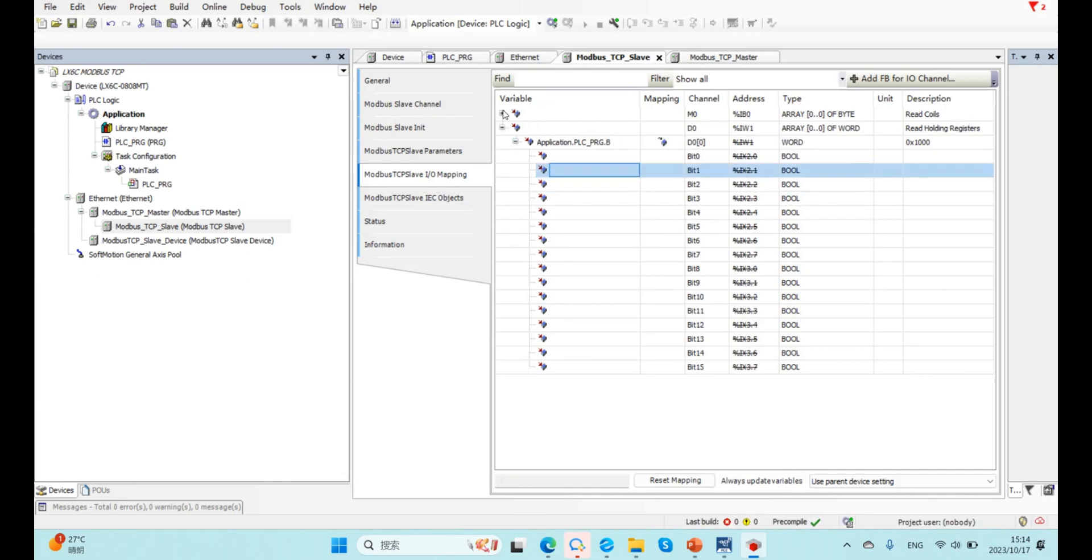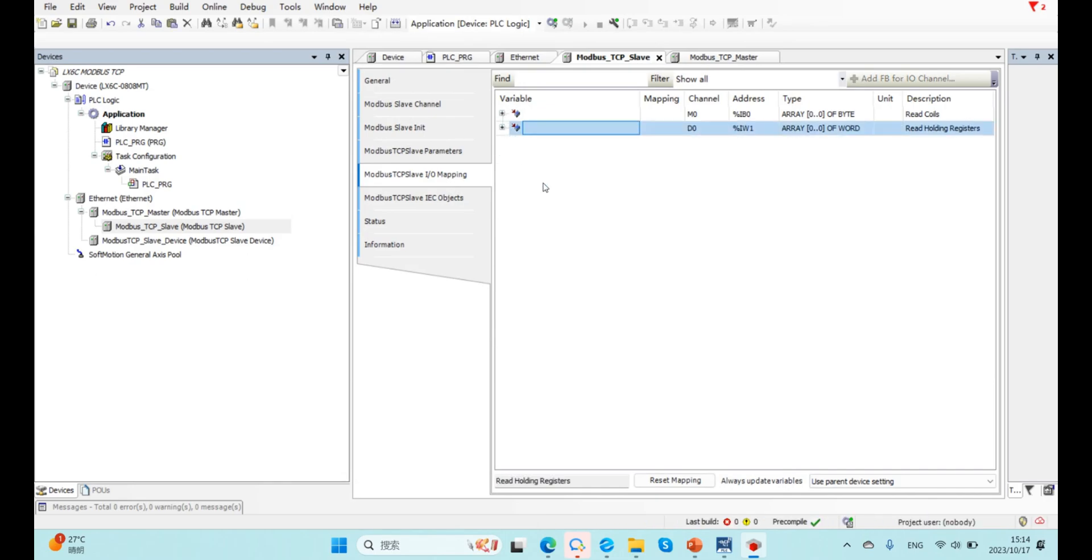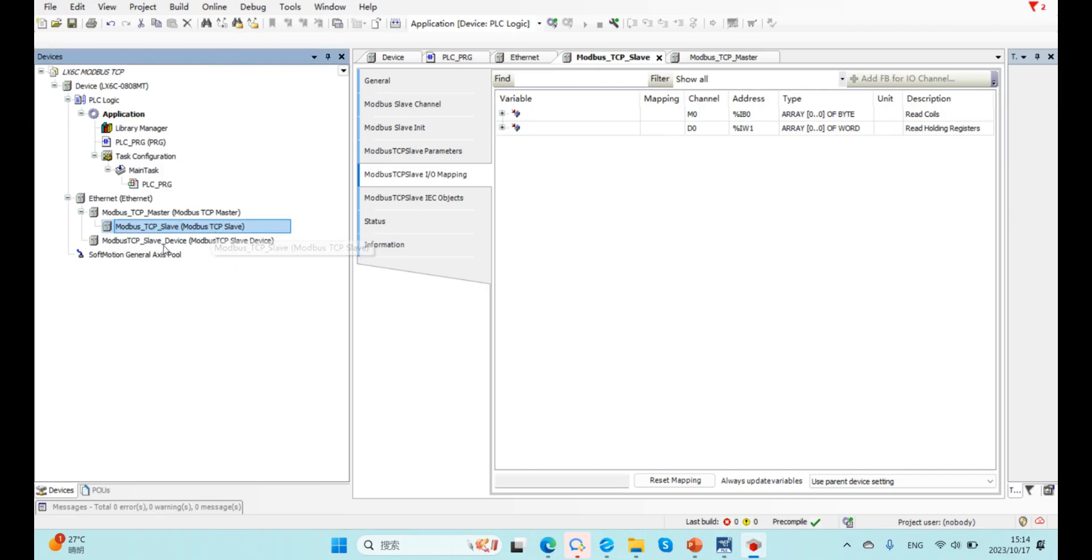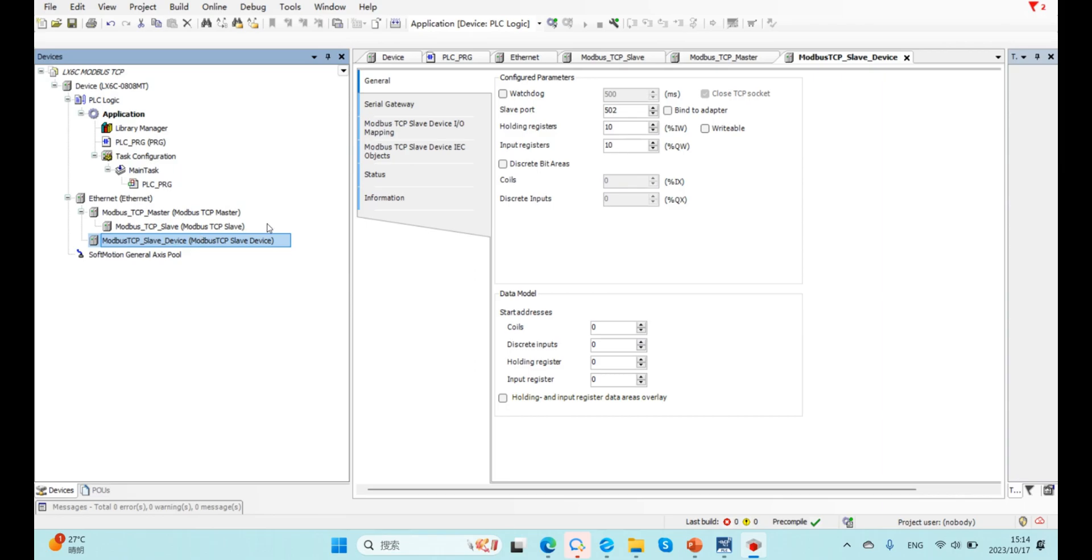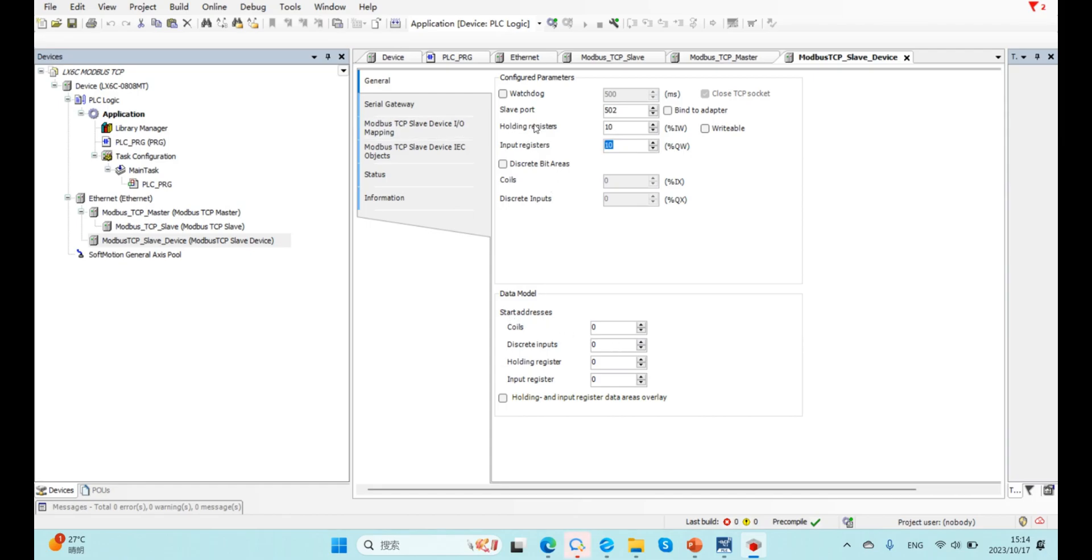So for first configuration is finished. Now, let's configure this. In this communication, our PLC is Modbus server. So here we can see the holding register length, input register length, and also the start address of this register. Here, we can change it to 100. Here, we use default value.